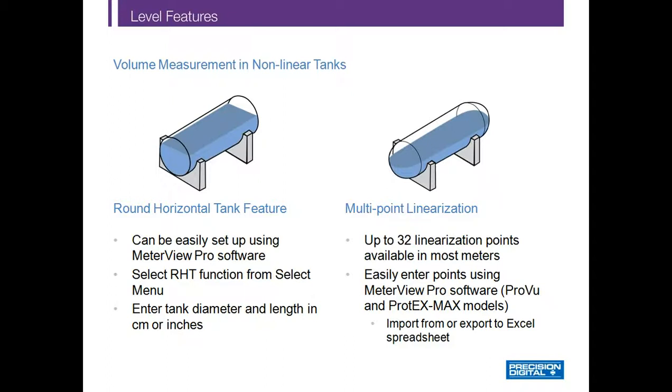For round horizontal tanks with flat ends, the ProVu process meter only requires the user to input the tank's height and diameter in either inches or centimeters, and the meter will calculate its volume. Multipoint linearization is available on most Precision Digital level indicators and controllers — if the tank has something other than flat ends, the user can input up to 32 calibration points to linearize the tank. These sophisticated features can be completely programmed through our free MeterView Pro software, available as a free download online.